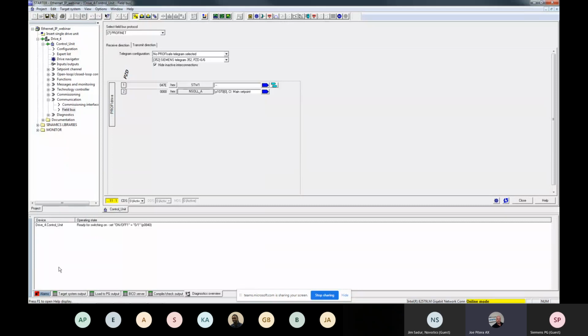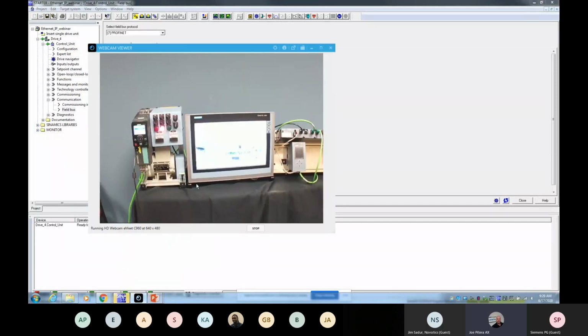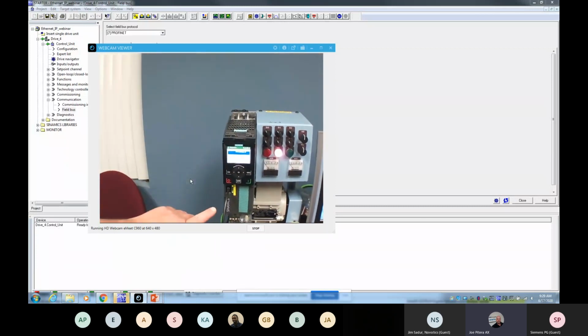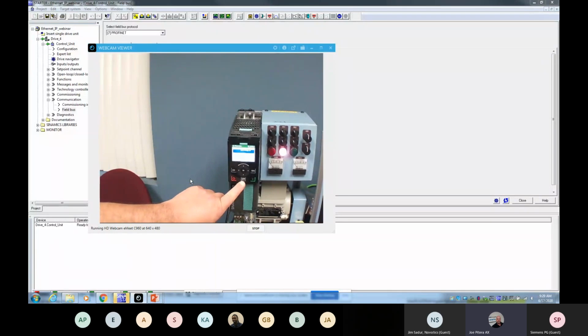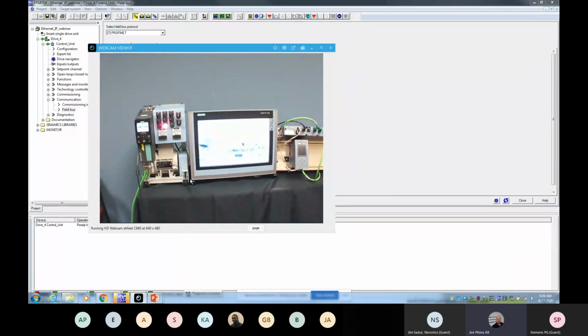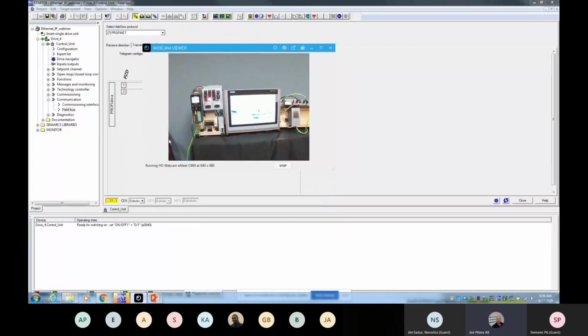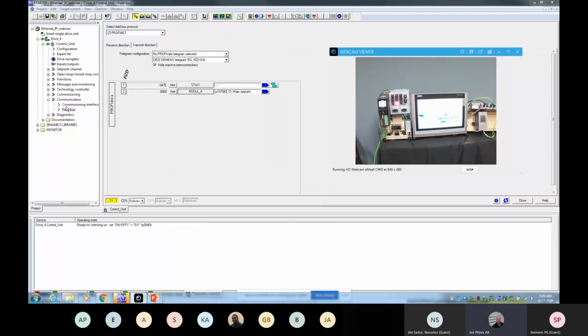We can either use the hand mode. I'm going to try and show this here. On the IOP, there is a hand mode we can use on the drive itself. And you can see that the motor ID active is currently set up on the IOP. But since this isn't so easy to see remotely, we're going to try and just take control of it from our software here, on their commissioning control panel.